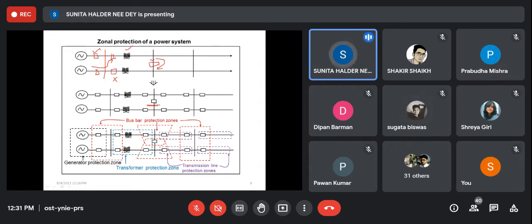So in the bus bar, say if there is a fault at this position, point A. Okay. And right here, say there is a point B with a fault. Can you see the point B as I have drawn? Yes, ma'am. If there is a fault here, then what will happen? The total bus bar will be grounded to zero. Now if you put a circuit breaker here, the circuit breaker will disconnect this faulty portion. So this bus bar will remain healthy, and power transfer will be possible through this transmission line for that reason.